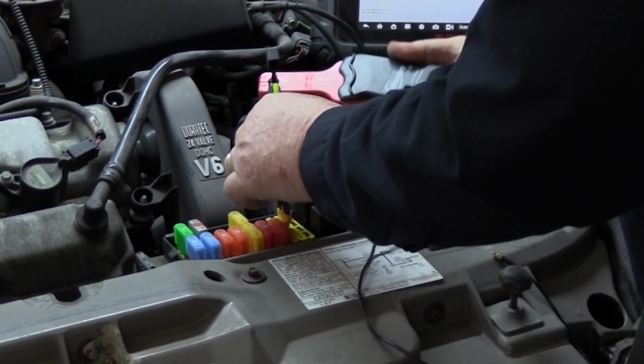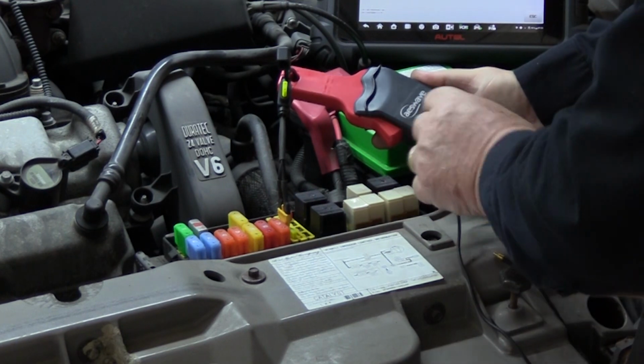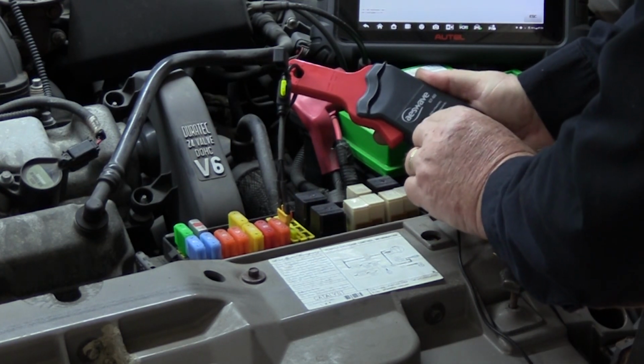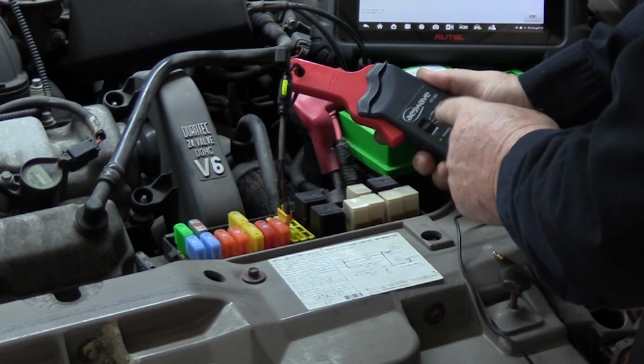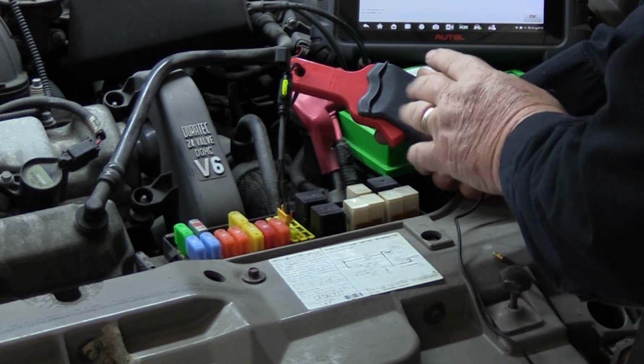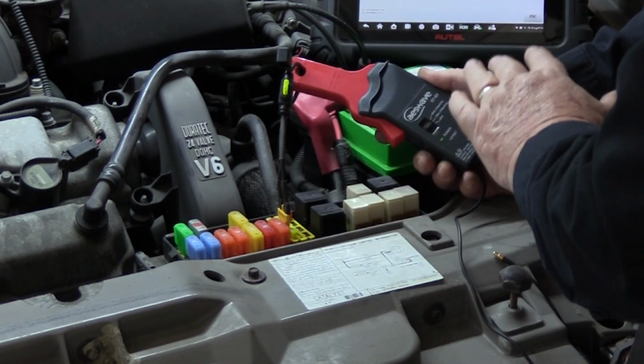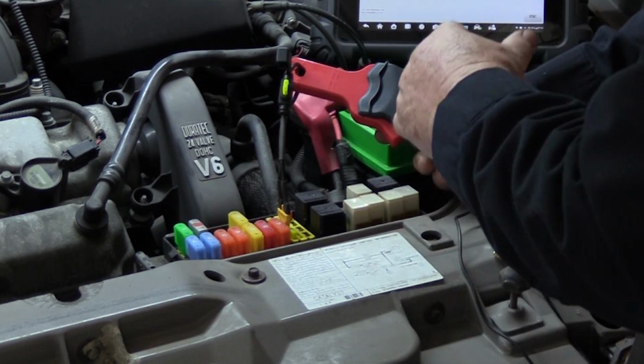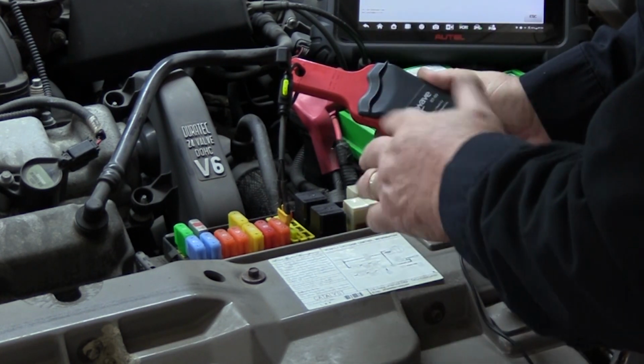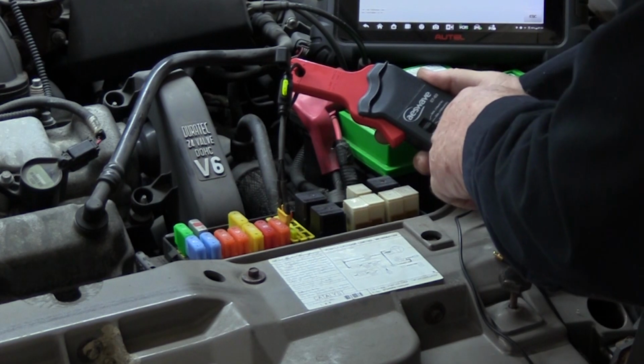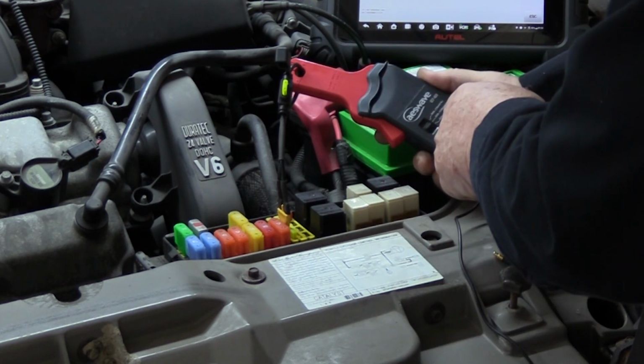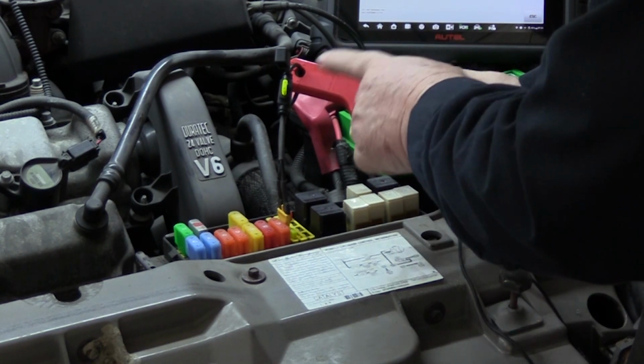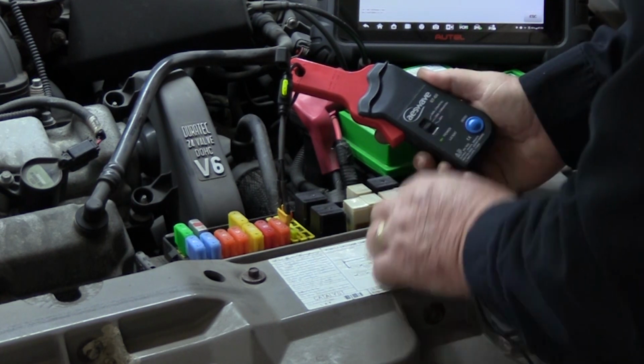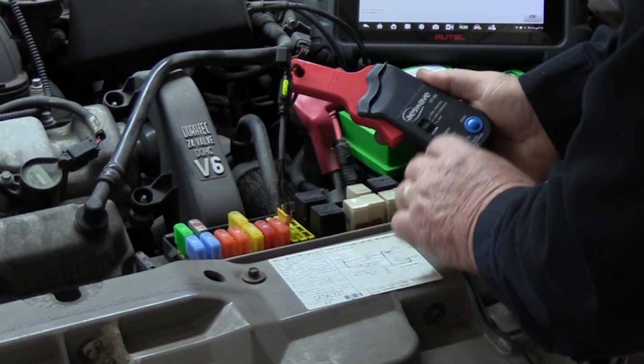We'll place that around the loop, and I'm going to set it to the 20 amp scale, which means this tool is going to output a voltage signal. Any probe you connect to your scope or multimeter sends out a voltage signal, nothing else. So a conversion is necessary: for every 100 millivolts this sends to my tool, that's equivalent to 1 amp. All right, I have that on, battery's good.